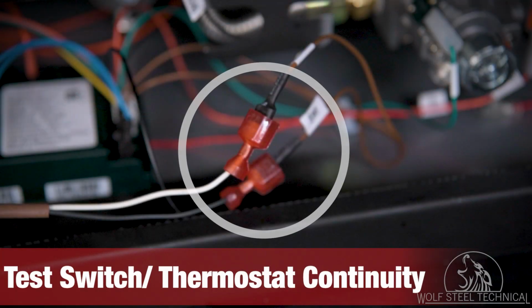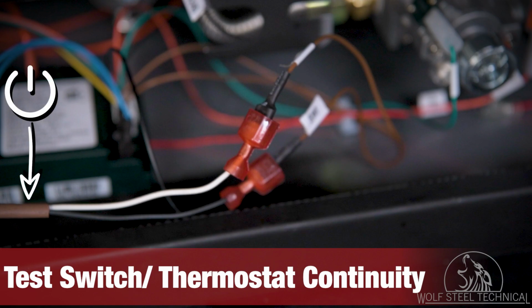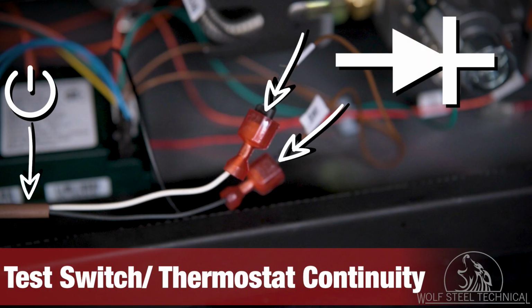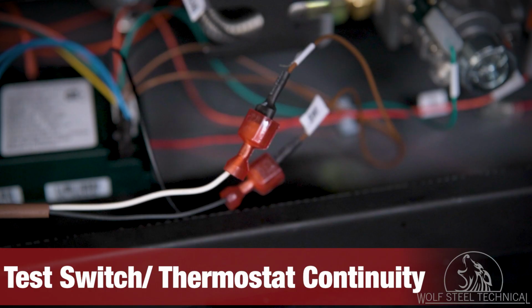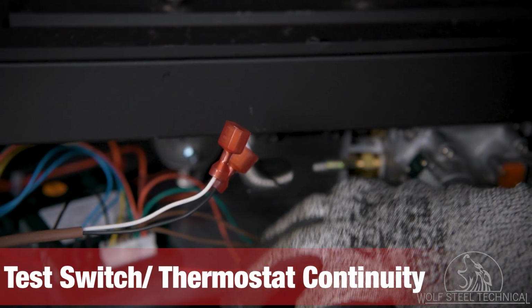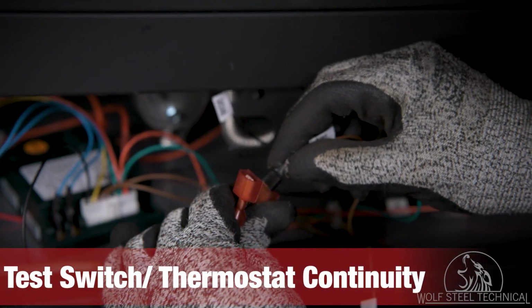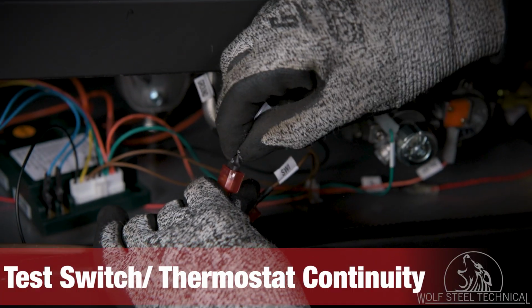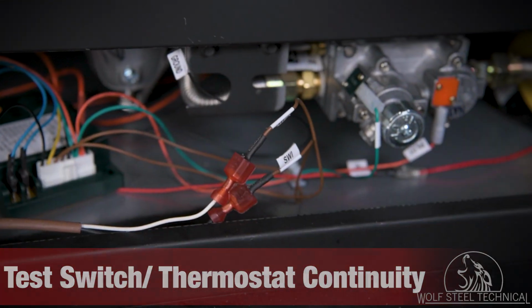Locate and disconnect the SWI wires in the control area. Turn on the wall switch or thermostat and connect the multimeter to the red spade connectors. This will test for continuity through the switch or thermostat. If there is continuity through the switch or thermostat, turn it off and reconnect the SWI wires. If not, turn your attention to the switch or thermostat wiring to ensure continuity.